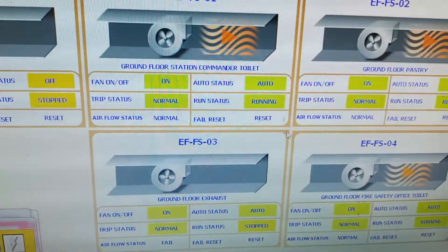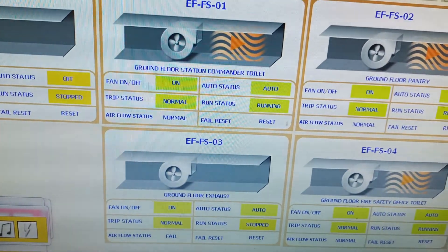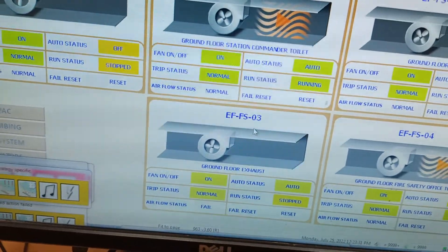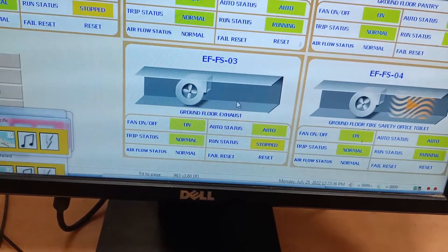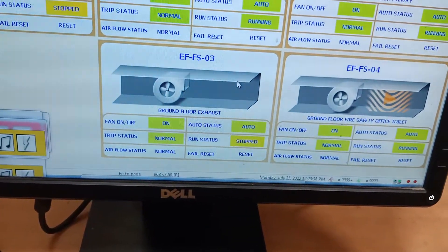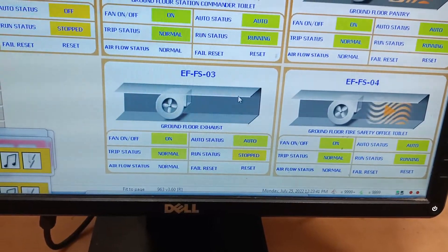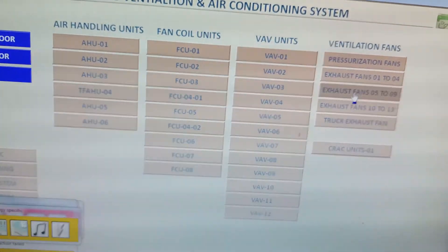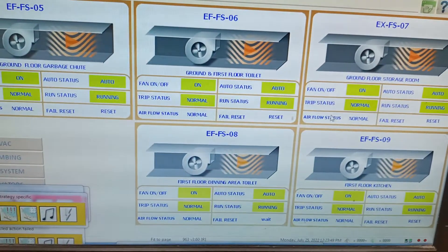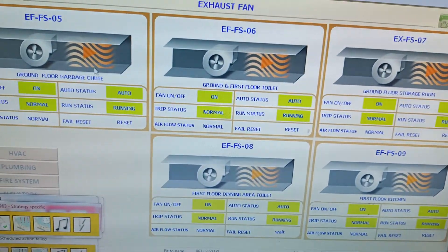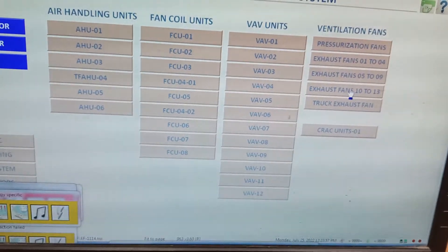Here you can see this is for an exhaust fan. We have four options: fan on/off status, trip status, and auto status. This fan is not running, so I will just reset it. Now it's showing normal but the run status is stopped — sometimes it takes time to switch on. Let's wait. The other one is working now. We will check another exhaust fan — all of these are running, so there is no problem here.